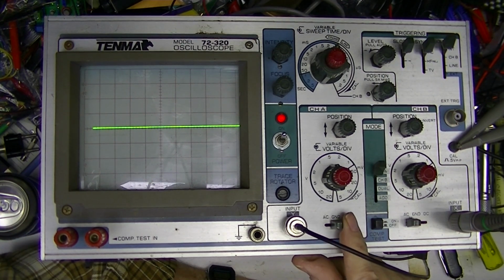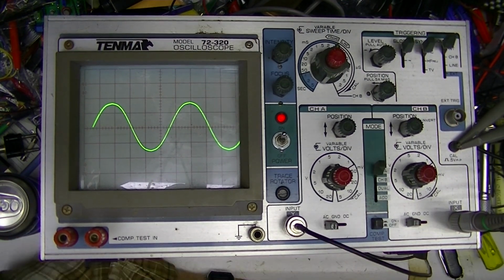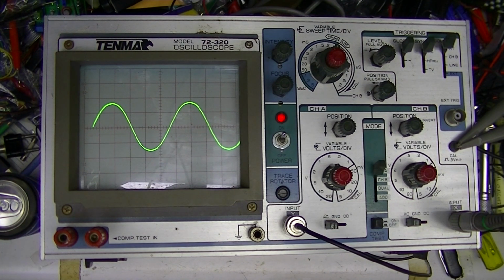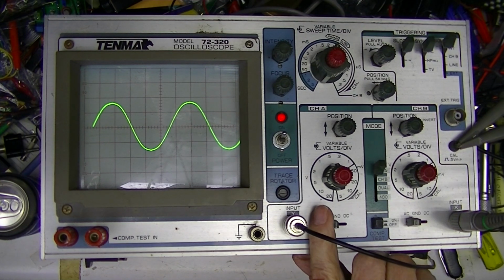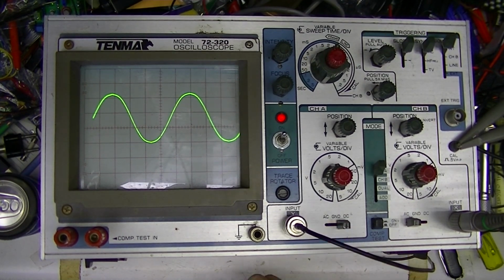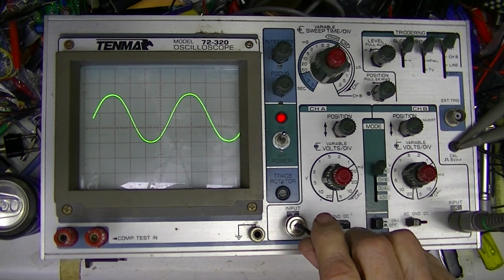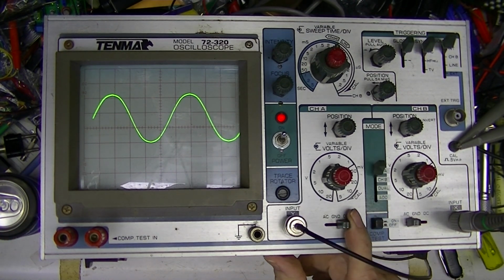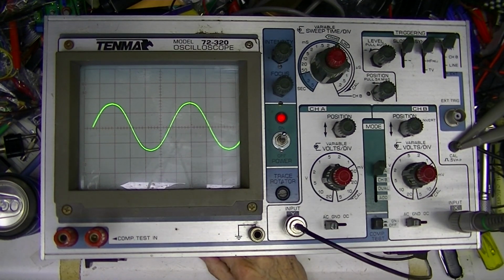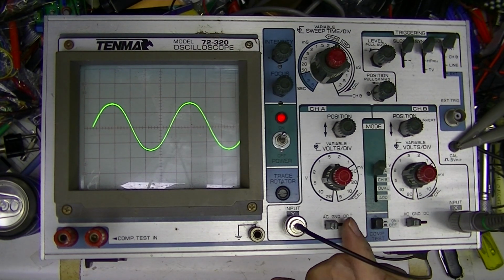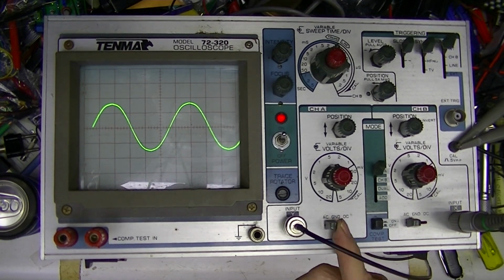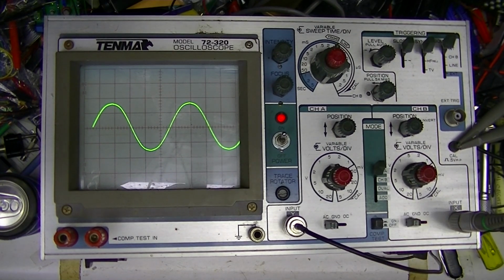Now we'll look at AC. AC will be centered around 0, assuming it's a symmetrical signal. DC may not be centered, depending on whether there's any DC coming in as well as AC. I always, unless I'm doing something special, leave these on AC coupling, unless you really want to measure the DC component.